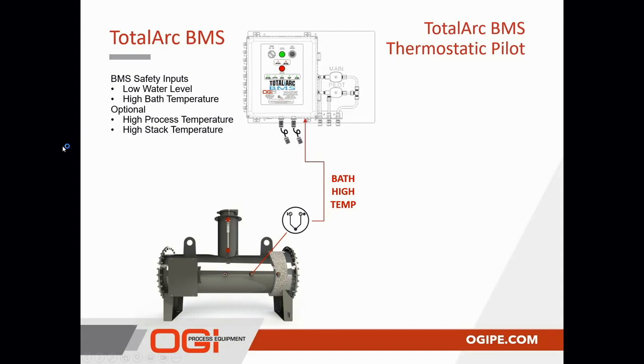The pilot can be set up for either intermittent or thermostatic/standing pilot based systems, and the configuration between whether it's thermostatic or intermittent is simply set up through a jumper in the control panel for the BMS.